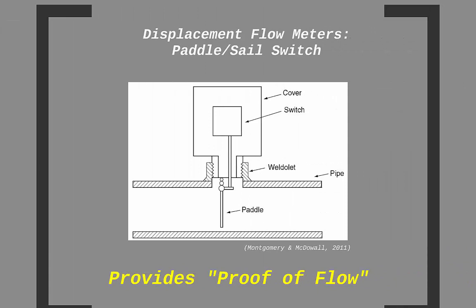Remember earlier when I said we often install sensors to prove flow is actually occurring? The example we gave was the fact that we need to ensure that chilled water is flowing through the evaporator barrel of a chiller before the chiller's compressor turns on. Devices that are often used to prove such flow would also be classified as displacement flow sensors.